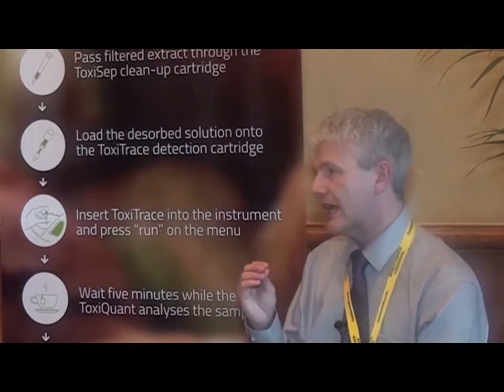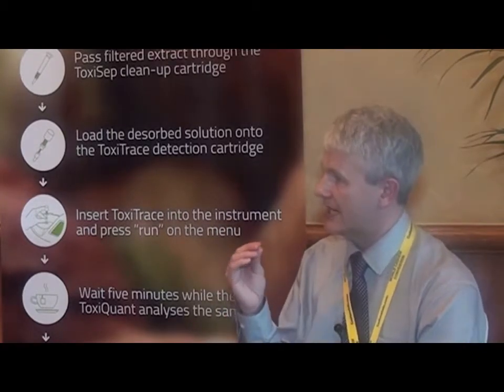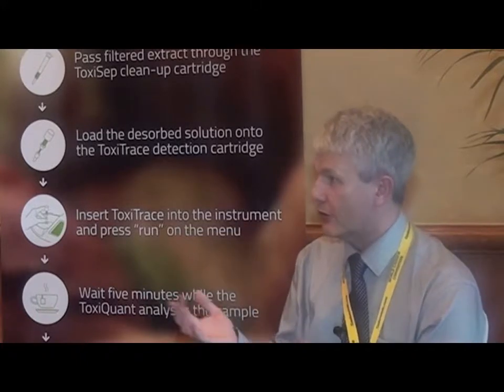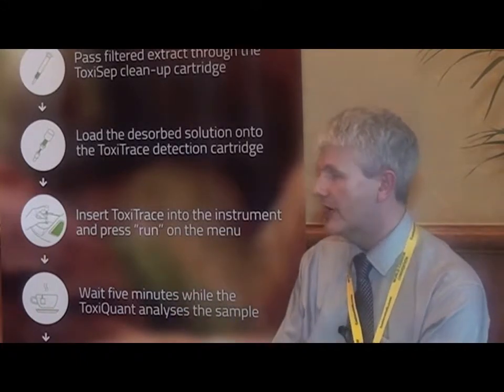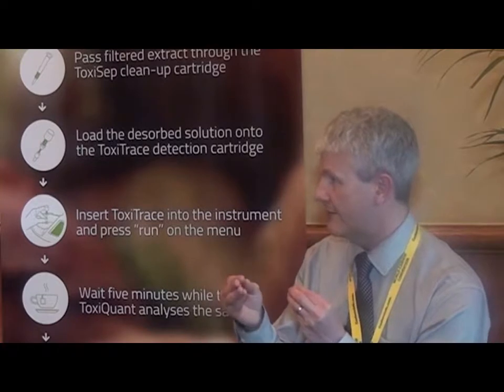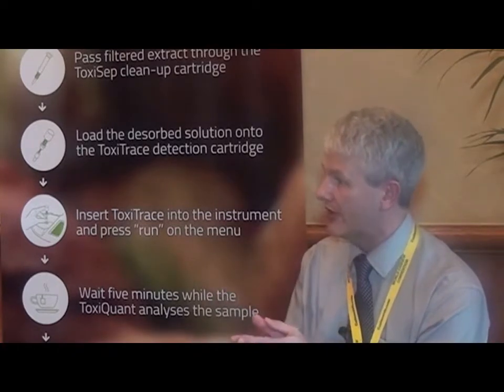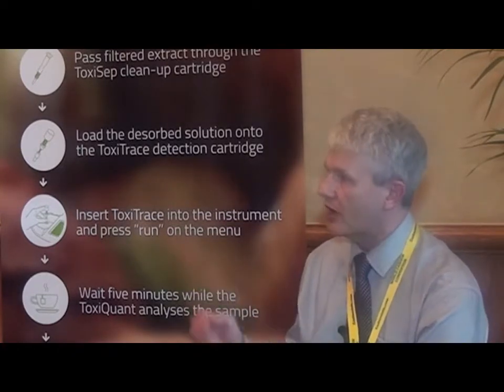It's measured using a fluorescence detector, like a spectrometer. We use a light-emitting diode to produce light wavelengths for the blue and green light emitted by the aflatoxins, and those are measured by the spectrometer. Each of the wavelengths of the light is separated, and we get a result for the 4 aflatoxins and for the total. Our machine does that all automatically with no calibration, so it's ideal for the processing industry.